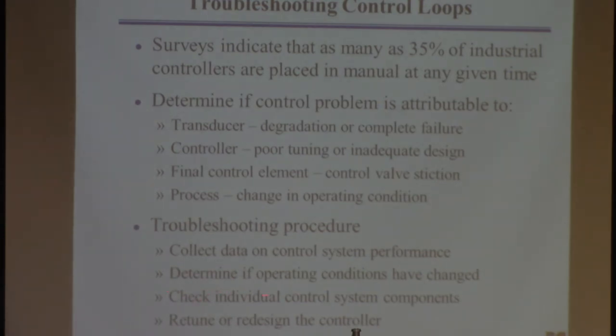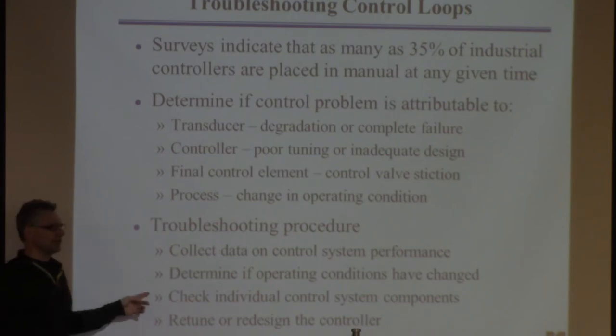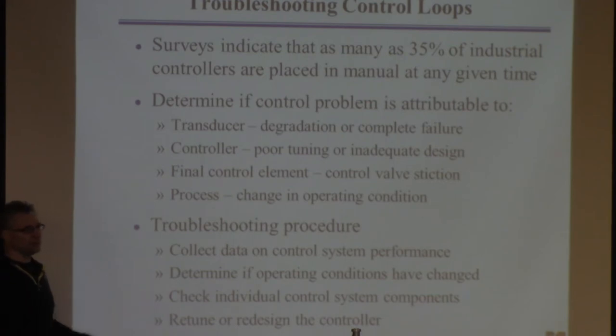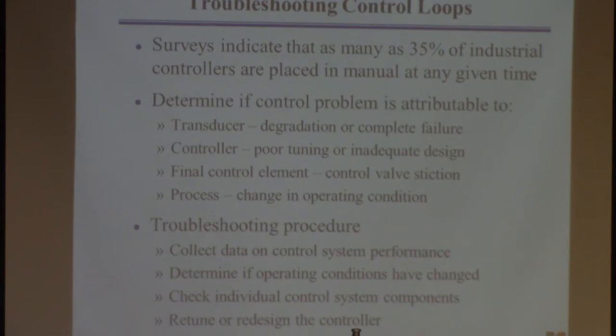Luckily, you don't have to do this, but you send someone out in the field. Like you say, you know, the temperature control on the heat exchanger is not working. Please go out there and check it for me. Please go out and like check the thermocouple, check the valve that's controlling the cold water flow rate in, make sure they're working. And then ultimately you might actually have to redesign, retune or actually redesign the controller.